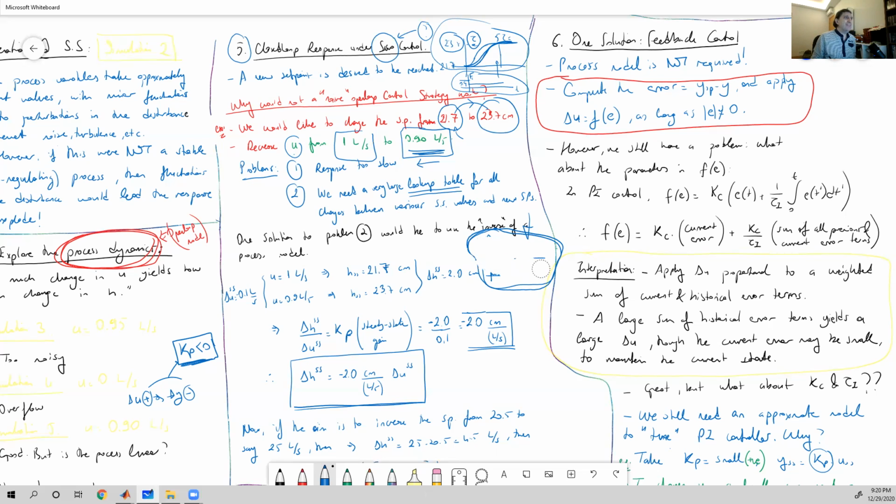Okay, so even that strategy of just using memory or previous experience is not a very good strategy, because bringing the system to a constant outlet flow rate and maintaining at that value is going to be a too slow response, because we are just going to be content with only the open loop time constant. But probably you know from your process control lectures, when you run the system in a closed loop manner, the closed loop time constant is much smaller than the open loop time constant. And one of the reasons why we use closed loop processes is to speed up the response of the process. This is achieved by changing the velocity, the inlet flow rate. We do not just make a step change and let it go that way. The manipulated variable changes automatically.